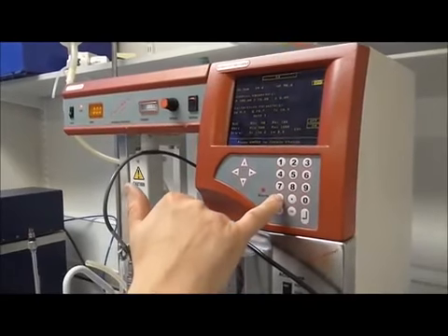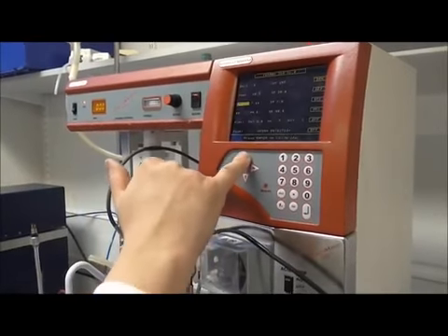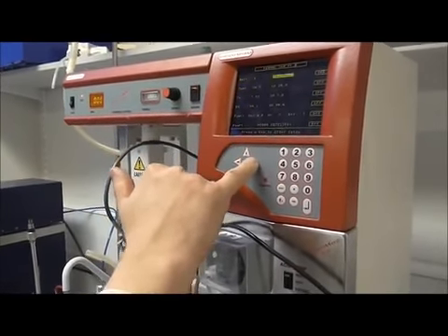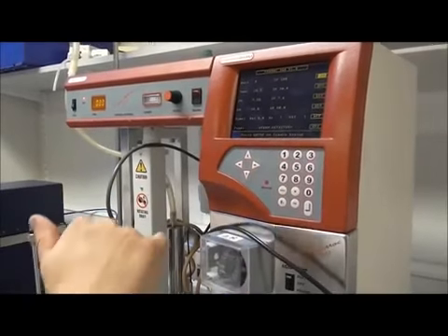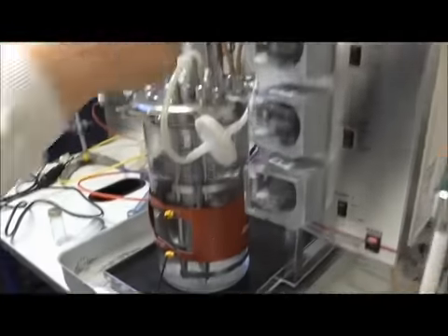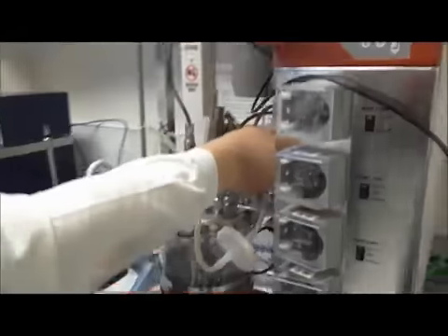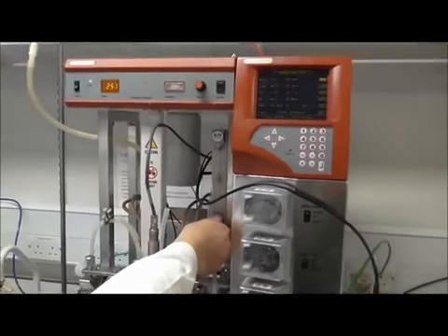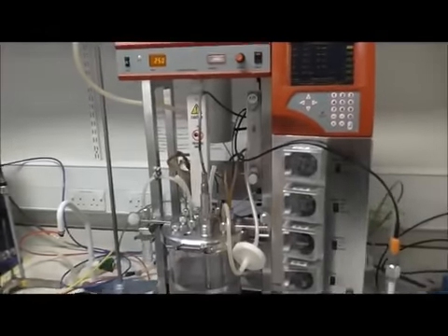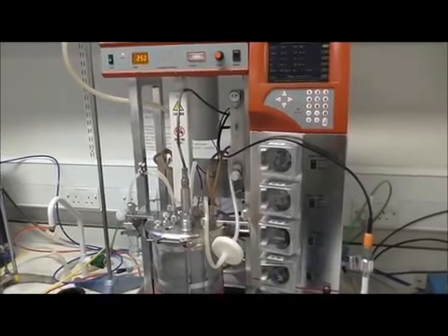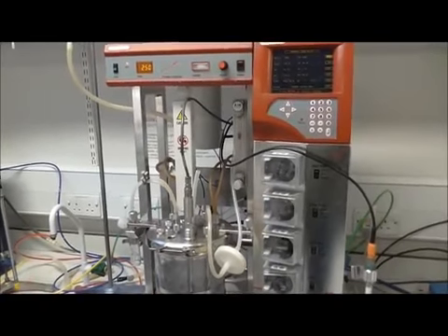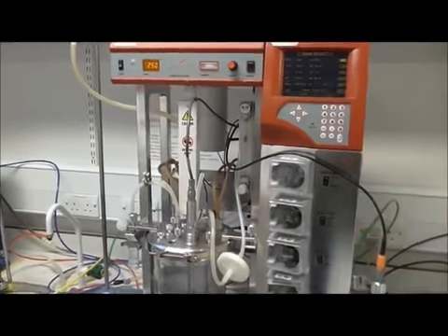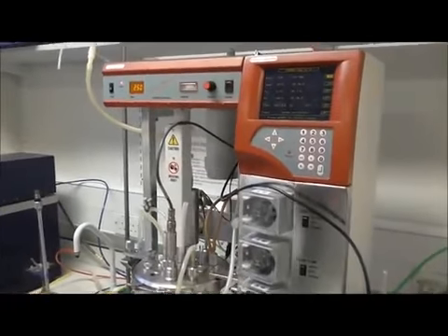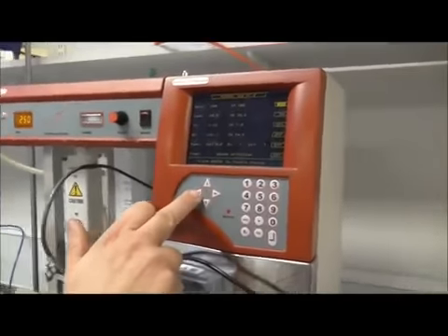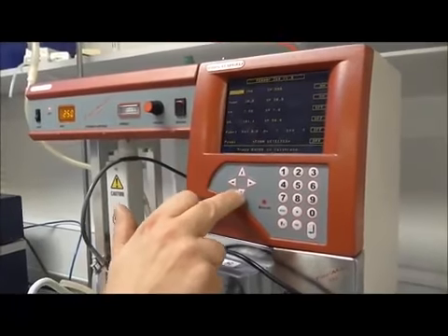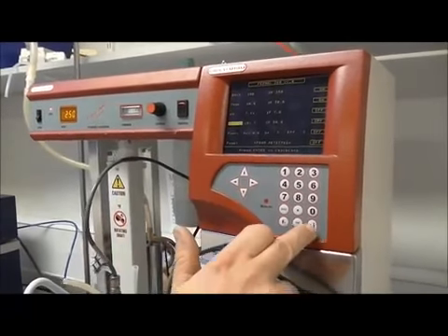So we need to come back out again. We need to get the stirrer going. On. And we need to set an airflow rate. I'm just turning the rotameter up to 4. 1 vessel volume per minute of air, so 4 litres per minute going in for 4 litres of water. We shall return to the dissolved oxygen menu.